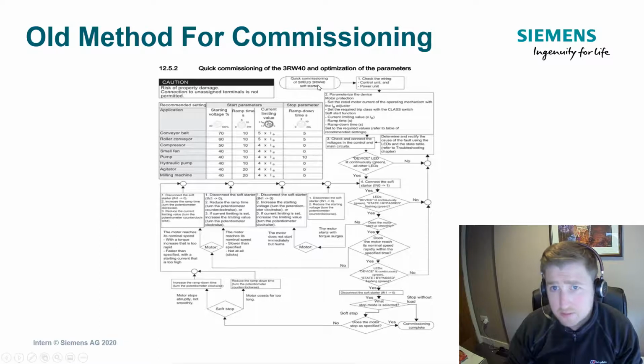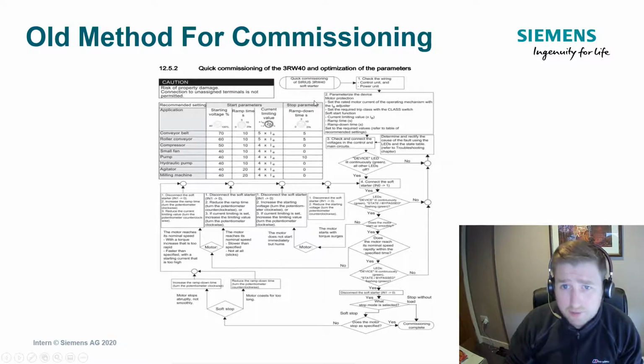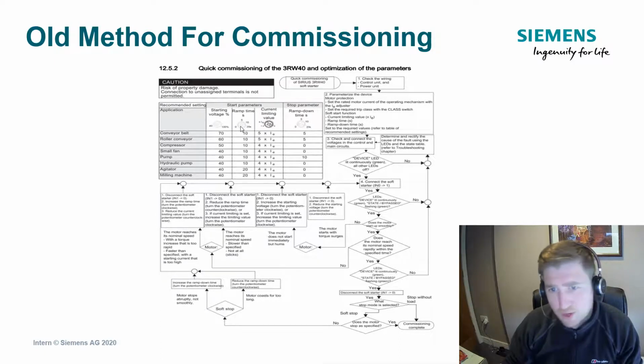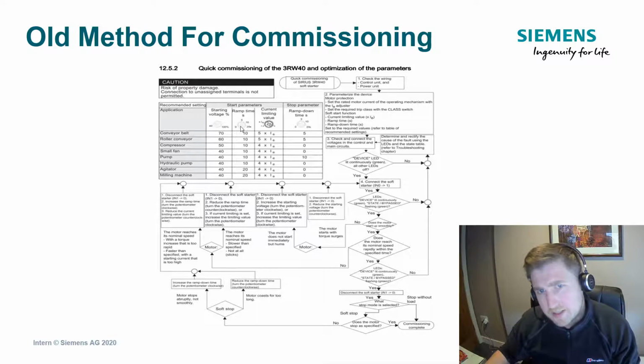And as you can see here, you've got a bit of a ladder or flow chart which basically depicts how you would react under the various different scenarios that are the outcomes dependent on what you've set those pots to. So the older commissioning method for programming soft starters was guesstimating. It was done through trial and error. Does that work? Does this parameter set work? No. Okay. Well, let's tweak the starting voltage. Let's up the ramp up time, and you go off trialing and second guessing what you might need to change.